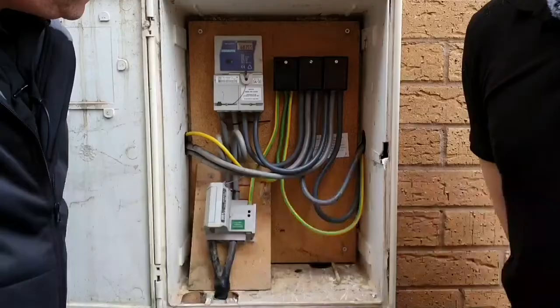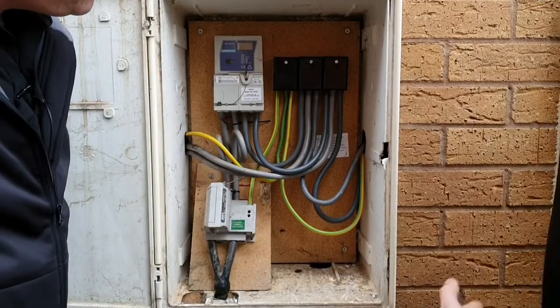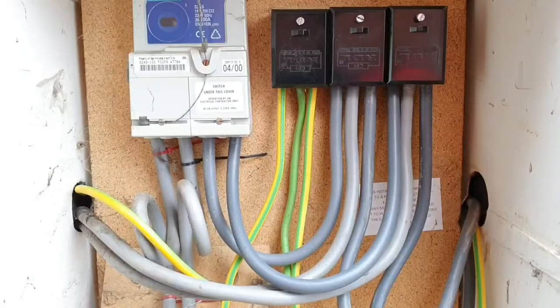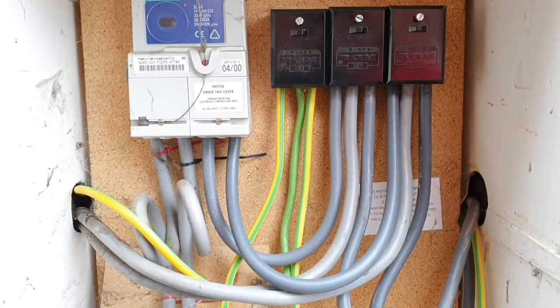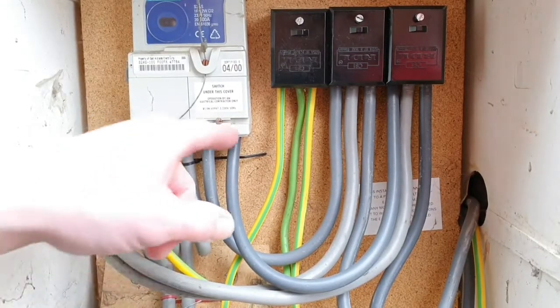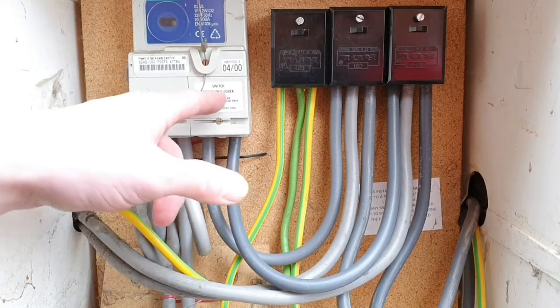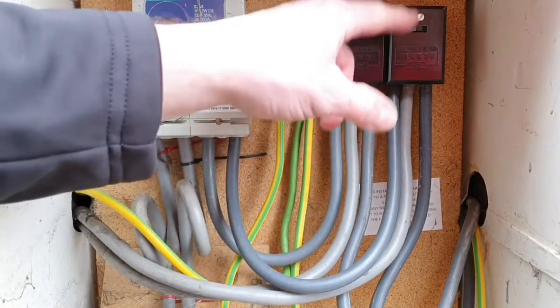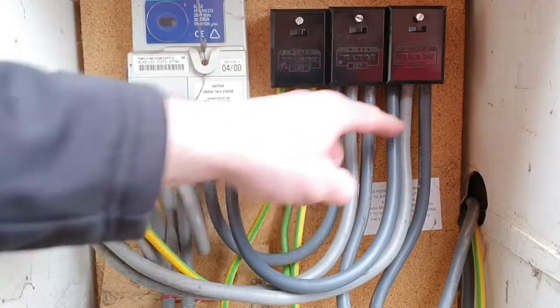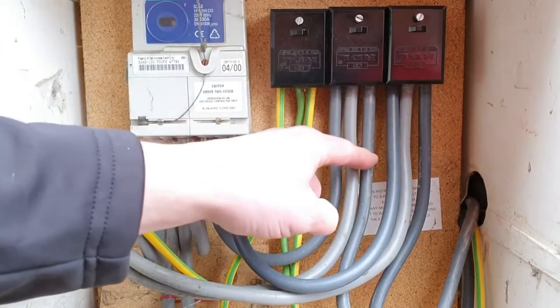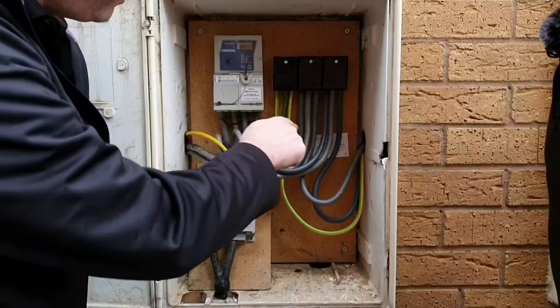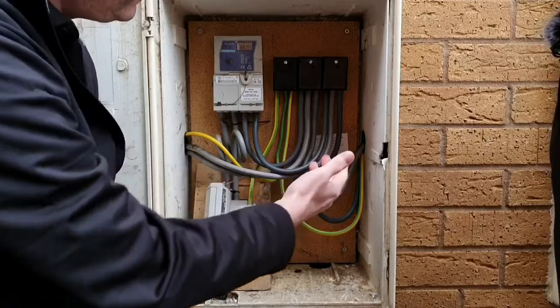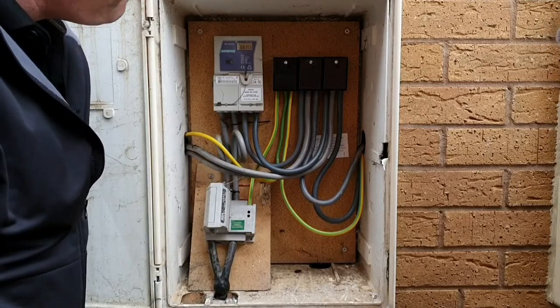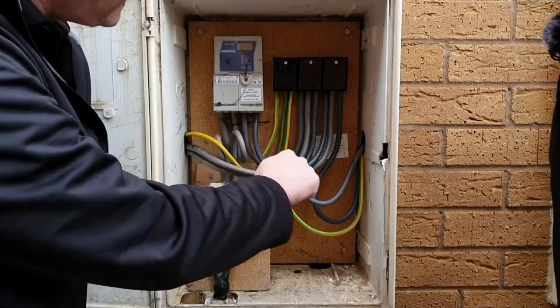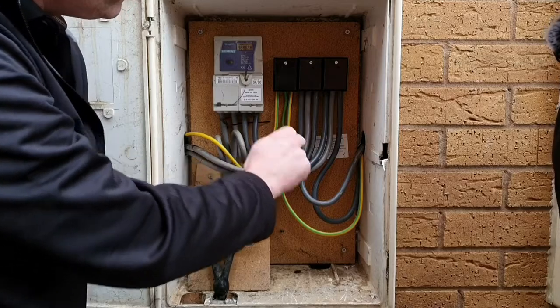Okay then, Gary, so we've now got a jumble of cables inside here. We've got a lot of tails going on. So can you just explain to me what's happened inside here? Yeah, so we've split the tails from the kilowatt hour meter, taking our supply into our Henley blocks up here, and we've got the outgoing line and neutral to our new consumer unit, and then we've got our original neutral and line for the consumer unit within the dwelling that was already there. And obviously we've got the supply tails coming in with both our neutral and line here.